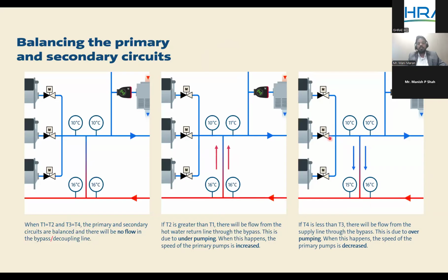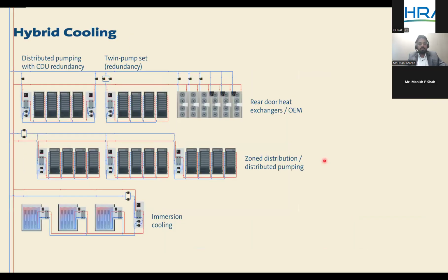On the return side, if there is more flow on the primary and the load on the secondary side gets reduced, the excess flow from the primary gets bypassed through the decoupler, and it impacts your T4, where ideally it should be 16, but it now moves to 15. So by identifying this scenario, we will reduce the speed of the primary pump. It's pretty simple. The balancing can be done at any point of time by identifying this temperature difference across the decoupler. So let's see a different configuration where we can put this concept in a data center.